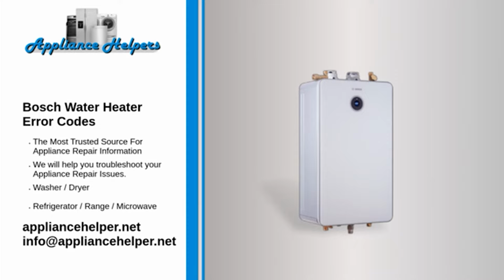Code E2. Problem. Faulty inlet water temperature sensor. Fix. Check the sensor and wiring connections, as this sensor is in charge of protecting the unit from freezing. Code E3. Problem with the exhaust temperature sensor. Fix. The unit will shut down if the temperature of the exhaust gases is above 194 F. Check and clean the heat exchangers if needed. Reduce the maximum power and water temperature.